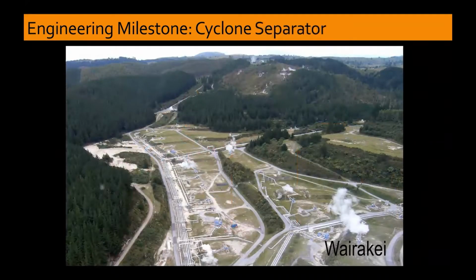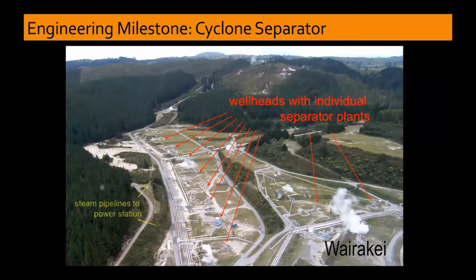This view of the western bore field at Wairakei shows that each wellhead has a dedicated cyclone separator. Steam is collected into a manifold pipeline and then transmitted to the power station. Such steam field design is dated, and in modern production fields, a cluster of wells serves a single separation plant, like at Ohaaki. The main thing is to emphasize the impact and role of engineering and the design of fluid collection systems in making geothermal energy work.